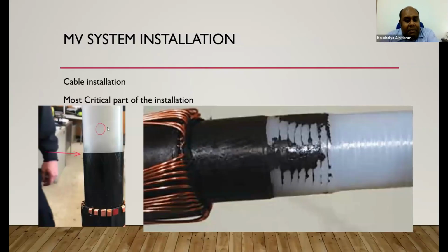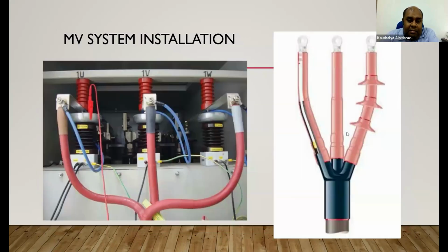Cable installation, the most critical part. If you see, there's a small black dot here in this circled area. Do you believe that's the ultimate culprit for the blast of this particular cable or flashover of this particular cable? That's the residue left during your cleaning process of the semiconductor layer, which will formulate partial discharge in the longer run. And this is another example, with higher bending radii than required. This is the right formation during the installation of your medium voltage termination kits.